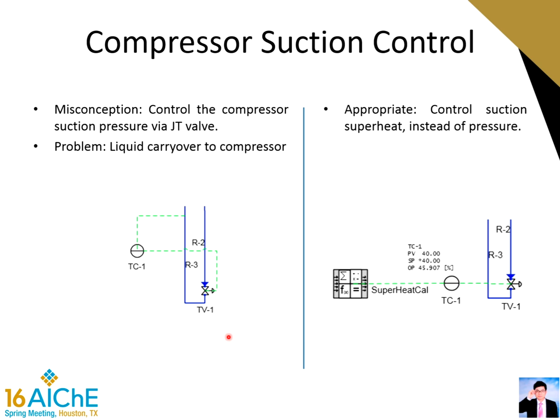When it comes to compressor suction control, it is quite counterintuitive. Common sense leads us to control the compressor suction pressure by manipulating a control valve. However, the problem is the operator might specify the wrong suction pressure set point, which may lead to liquid carryover to the compressor. A better way to control the compressor suction is to control the suction superheat instead of pressure.